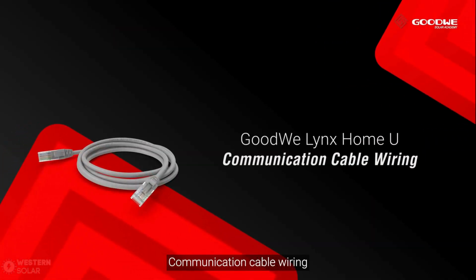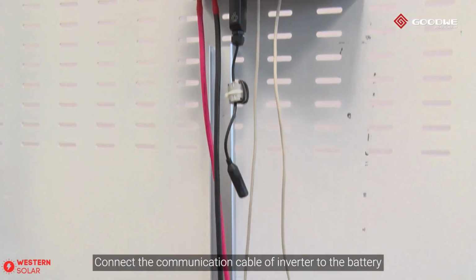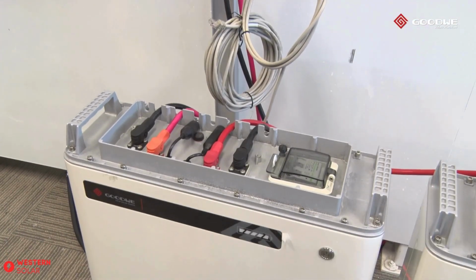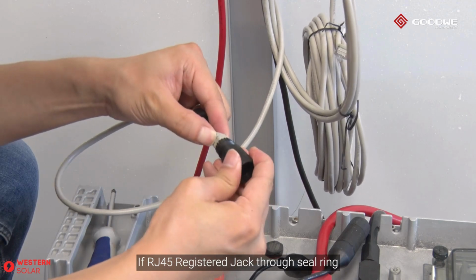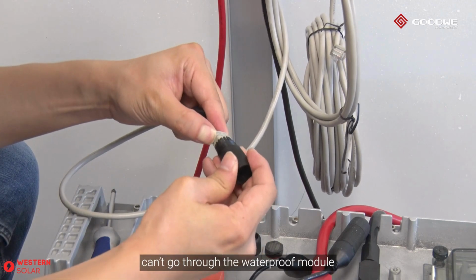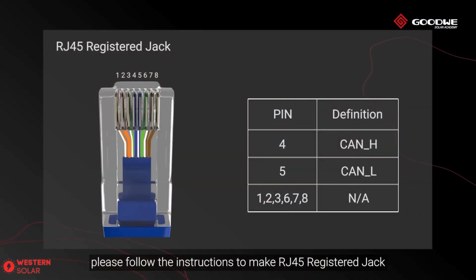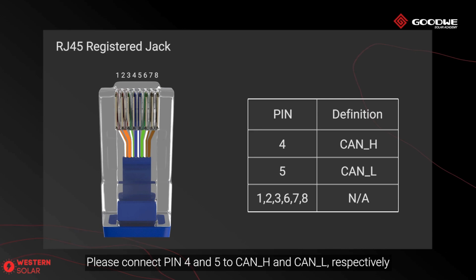Communication cable wiring: connect the communication cable of the inverter to the battery. If the RJ45 registered jack with seal ring can't go through the waterproof module, follow the instructions to make the RJ45 registered jack. Connect pin 4 and 5 to CAN H and CAN L, respectively.